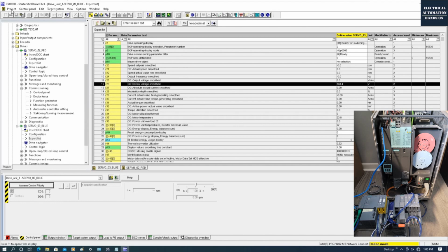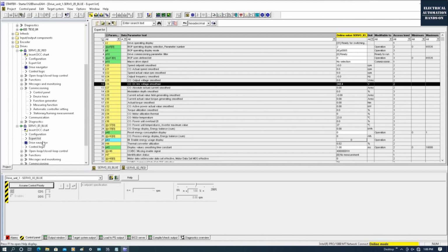Alright, in this video we used this Starter software. We started from scratch, set up a new project, and then did the factory restore. And after that we clicked the automatic configuration. And we found that Servo 3 we need to configure manually. Then we did the DDS manual configuration wizard. And after this, we uploaded all the configuration from the online CU to offline. And after this, we went online again and configured the expert list. In the expert list, basically, we need to configure the DC link and the input power, just to verify if the actual input power and DC link match with your setting.